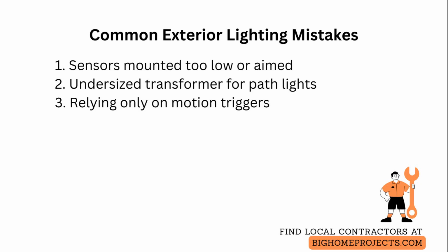People commonly place motion sensors too low or aim them toward glass, which causes reflections and nuisance triggering, so mount sensors at the recommended height and point them away from reflective surfaces. Another frequent mistake is undersizing the transformer for low-voltage path lights, which leads to dimming and reduced lifespan, so calculate total fixture load and add a margin of at least 20% when selecting a transformer.